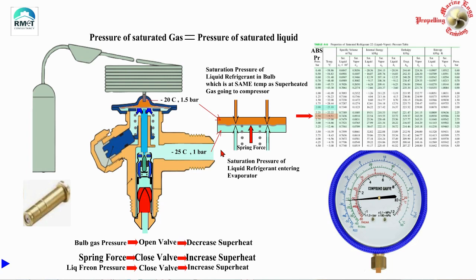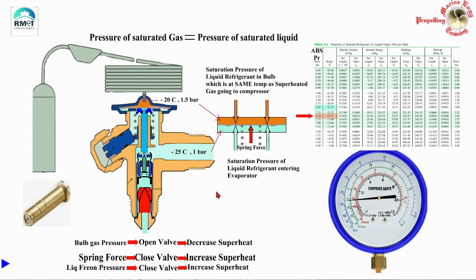If more refrigerant enters the evaporator, it will not have the opportunity to completely convert to gas before the exit, so there is a possibility the refrigerant will still be partly liquid when exiting the evaporator. That is why closing the valve gives a better chance of increasing the superheat. You cannot easily adjust the suction pressure since it is set at minus 25 to keep the meat room at minus 20, but you have the spring, which allows a human to tighten it and adjust the superheat — that is why this is called the superheat adjustment device.